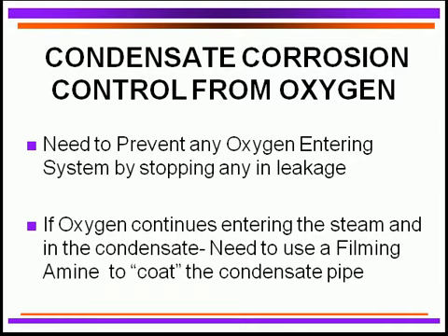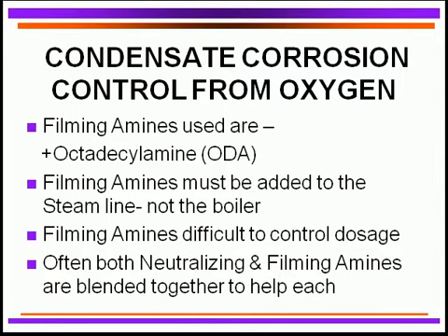If you can't stop oxygen from getting in, you need to coat the condensate piping with an oily-type film using filming amines. Octadecylamine or octadecylamine acetate is a very common filming amine. These filming amines cannot go into the boiler because they don't carry over with the steam, so they must be injected directly into the steam line. Controlling the dosage can be difficult, so filming amines are not used that often. It's preferable to remove the oxygen or reduce carbon dioxide before it reaches the boiler.